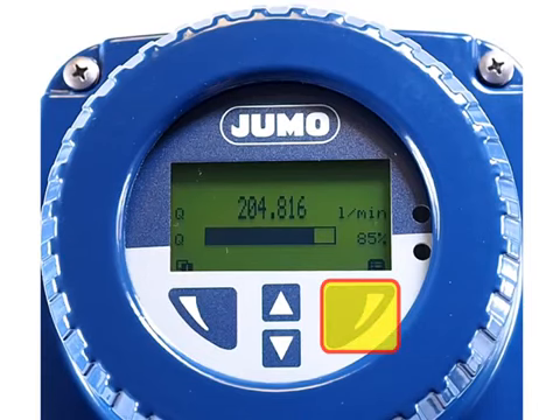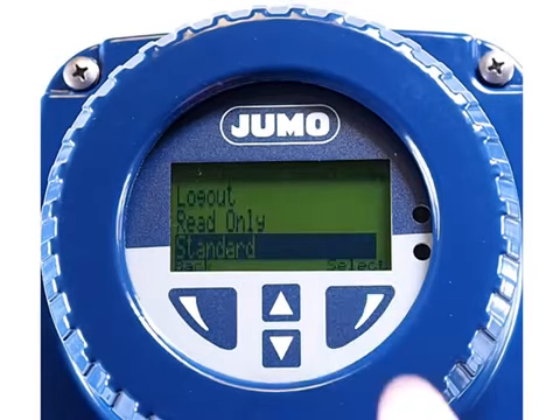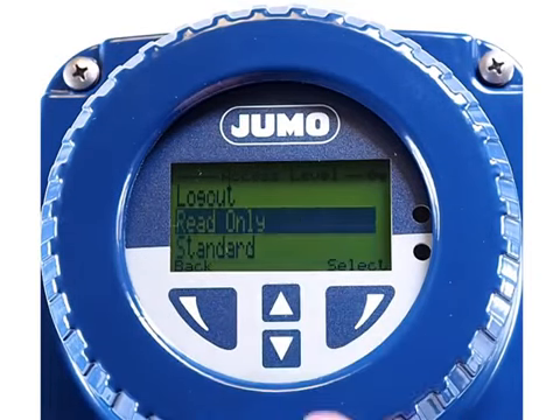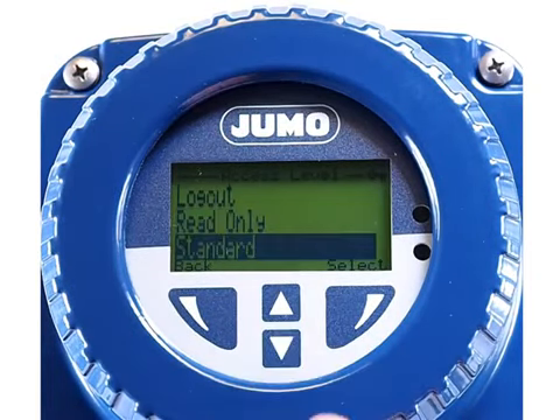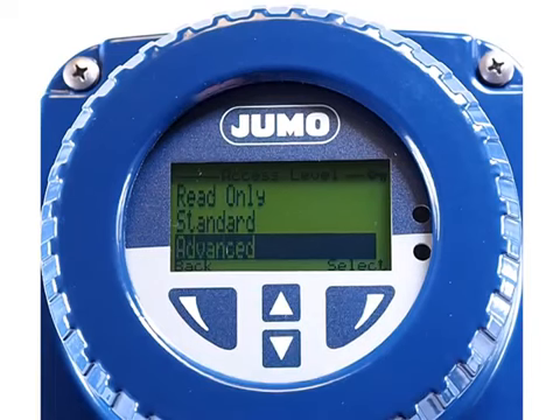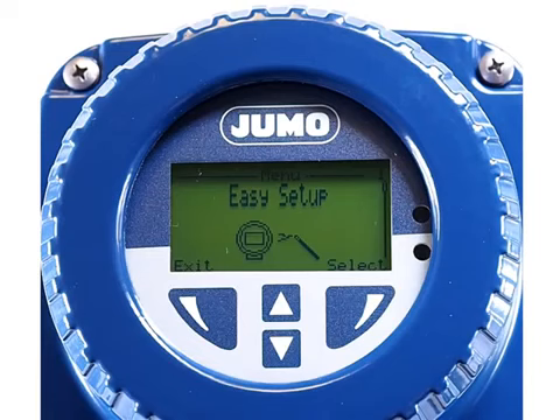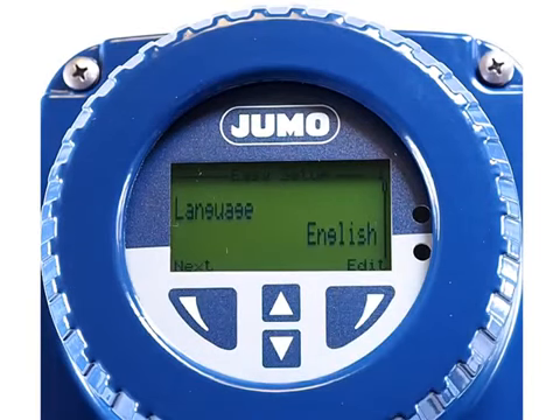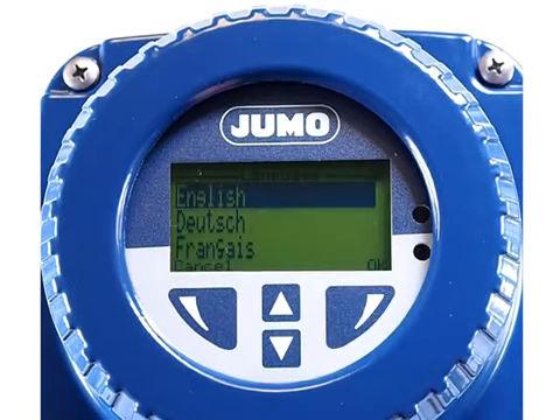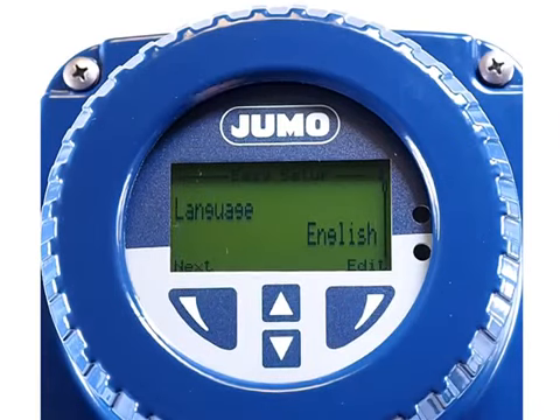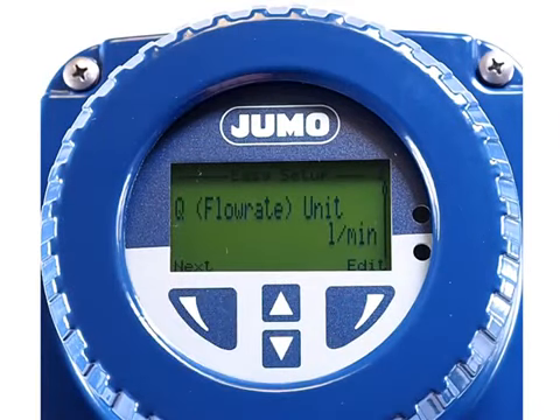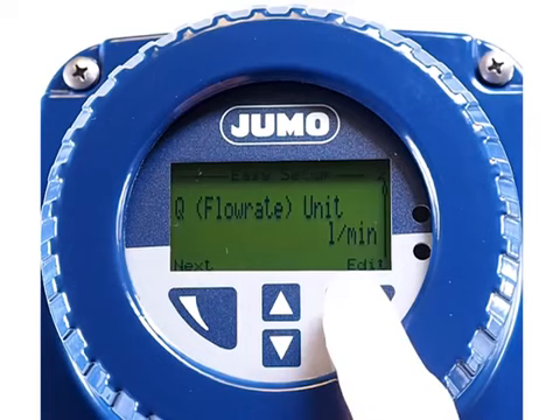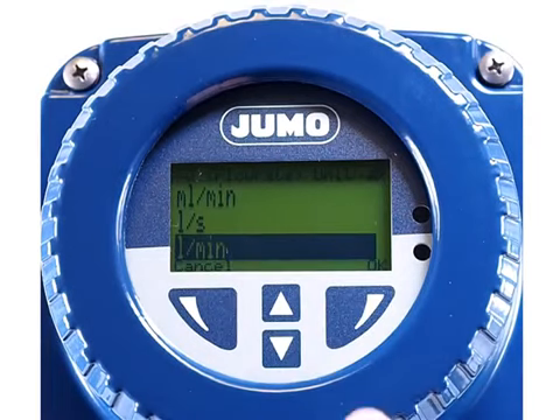The access level can be reached by using the right soft key. Here we can select between read-only in standard view or the advanced functionality. We choose standard and select the easy setup. In easy setup we will be guided through 12 different parameters, starting with the choice of the language. Up next we want to set the unit for the flow rate.